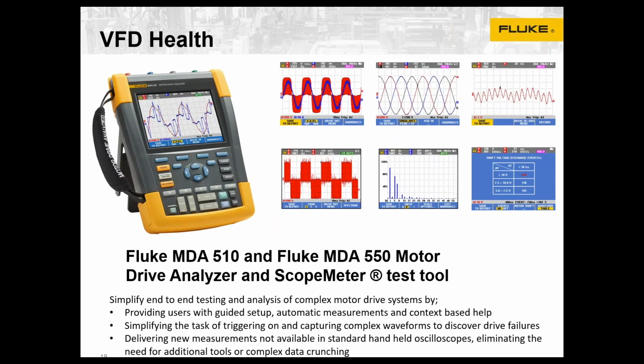VFDs are at the heart of many of your assets in a plant. And there's always been a challenge in, how do I know if I have a problem with the VFD, or is it the drivetrain, or is it my incoming power? A new class of tool called a motor drive analyzer helps automate that process and make that quick and easy. It provides a guided user interface, starting from, where do I measure? Drive input, DC bus, drive output, motor input. What are the pertinent health measurements? They're all listed in a menu.